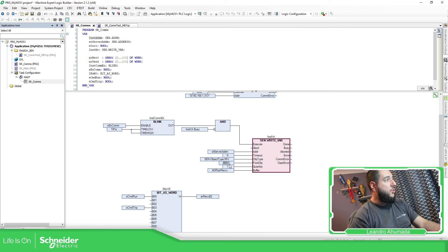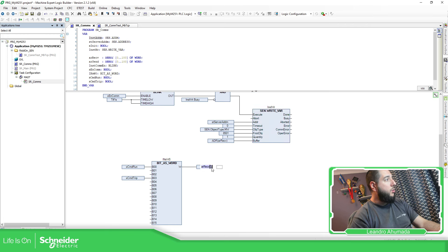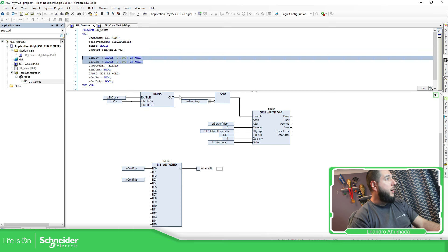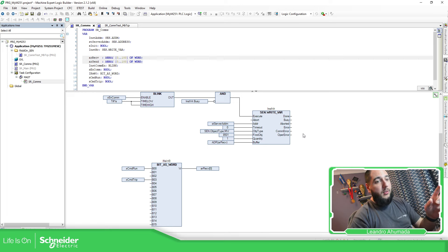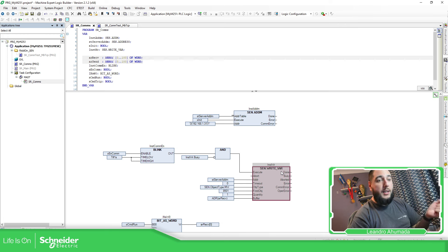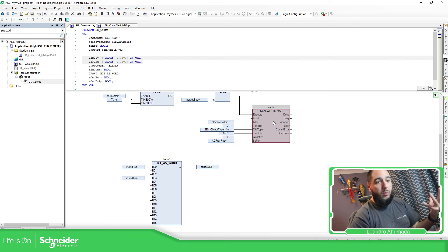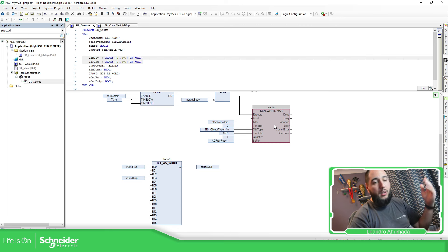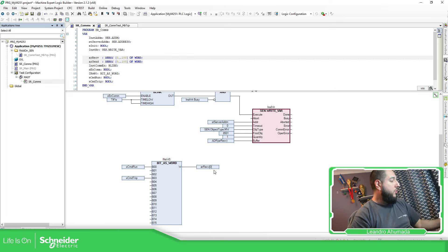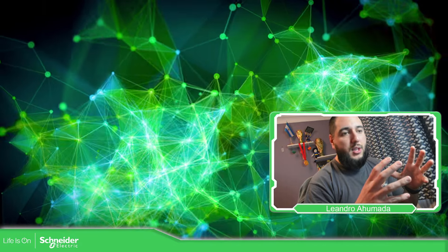So this is how you can work with the read and write function blocks. The read is going to be exactly the same — you just need to know the address and the quantity to receive, and how you're going to access the data that's going to be in the buffer. Having this structure is crucial in order to make it work. The other thing you need to be careful of is trying to call all of these function blocks at the same time, so having a cascade or step sequence in order to access each of them is going to be good. My recommendation is not to disable the call of the function block — the call is always called, but the execution needs to happen at the moment that you want.